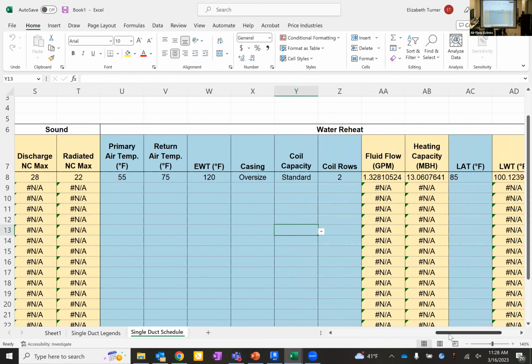So I've noticed that most schedules have an MBH, but not coil rows. I was taught that the MBH should be equal to or slightly above what the schedule says. So if you have, let's say hypothetically, the MBH is calling for 15 and a 1-row coil is 10, but a 2-row coil is 25. I know that wouldn't be the case. But what would you recommend there? Would you rather be 5 below what they're asking or 15 above? Or would you use an oversized coil there, or what's your recommendation on that?